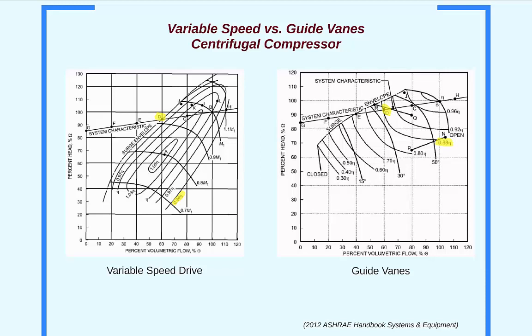As you can see at points F and G, both these control modes are limited in how low they can operate. At loads less than 40% for guide vanes and less than 60% for variable speed drives, the compressor is outside of its operating capacity. If the compressor needs to operate at points F and G, this can only be accomplished through the installation of hot gas bypass.